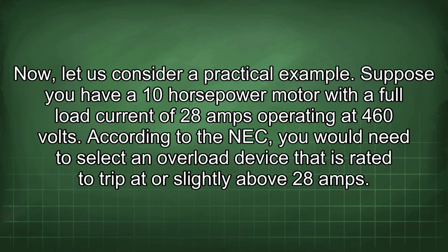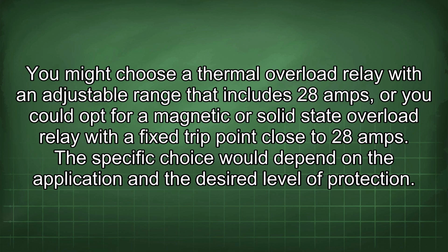Now let us consider a practical example. Suppose you have a 10 horsepower motor with a full load current of 28 amps operating at 460 volts. According to the NEC, you would need to select an overload device that is rated to trip at or slightly above 28 amps. You might choose a thermal overload relay with an adjustable range that includes 28 amps, or you could opt for a magnetic or solid-state overload relay with a fixed trip point close to 28 amps. The specific choice would depend on the application and the desired level of protection.